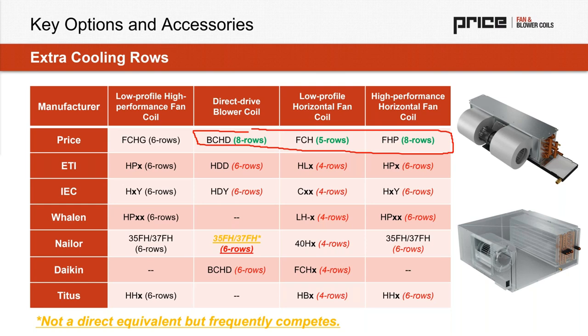that allows it to operate much more efficiently. Or it's going to provide a cost-effective solution because you, as a design engineer with a high load application, might be able to stay with a smaller size and footprint and lower cost piece of equipment with more rows rather than upsizing. So for instance, you could have a size 20 BCHD with 8 rows of coil instead of a size 30 BCHD with 6 rows of coil. And that's an option that's available with those additional coil rows that can help save cost and energy on projects.